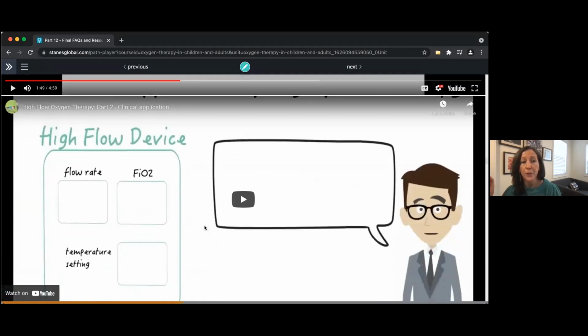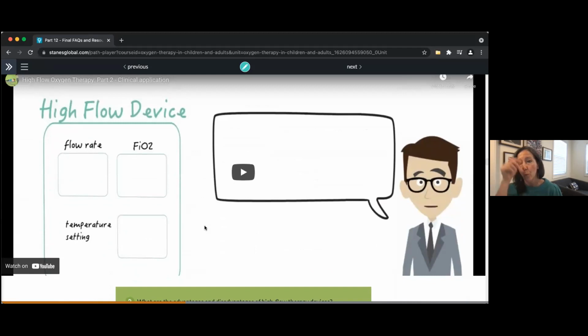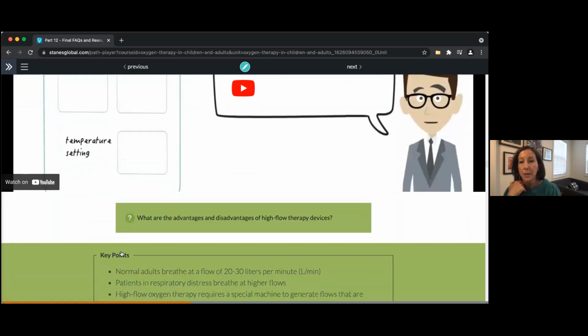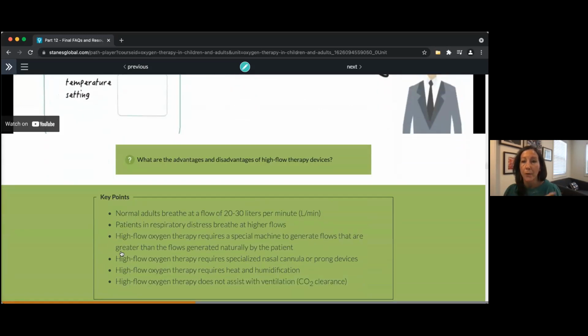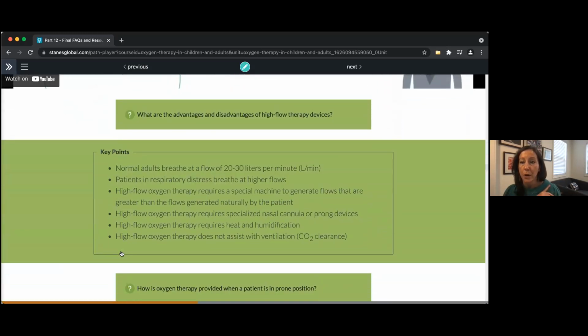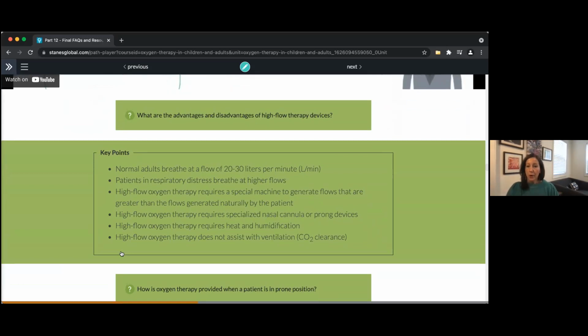So I encourage the audience to watch the second video, which goes into how to set the flow rate, the FiO2, and the temperature, which are the only 3 settings on a high flow oxygen therapy device, which is important to recognize because there's no volume set, there's no respiratory rate set, there's no pressure set. These are the only 3 settings. So you're really just setting the flow rate, the FiO2, and then the temperature. So high flow oxygen therapy is different, and it is a higher flow than what you can do with just a regular non-rebreather. So the advantages we already talked about.